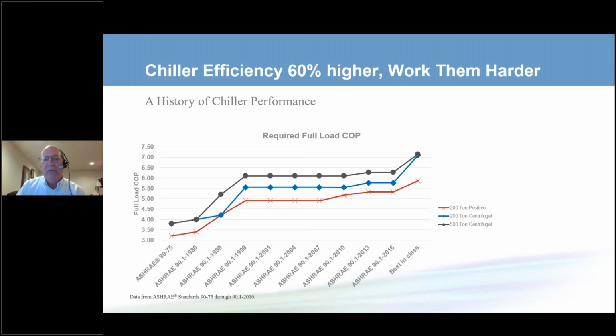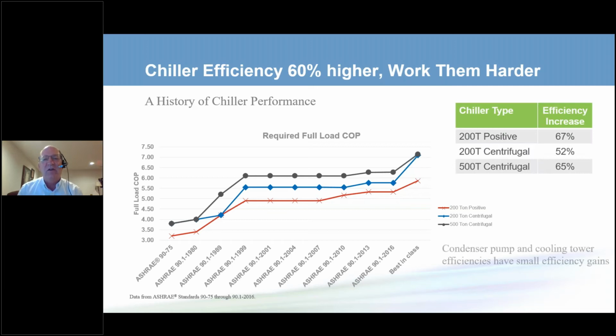We see that there's been a significant increase in the COP, and I really like that societies and cultures like yours use the coefficient of performance. That is, how much useful cooling do we get out of the chiller compared to the work put into that chiller. In the US, we use what I tell people are the wrong units. We use kilowatts per ton, and that's not a good measure of chiller efficiency, but COP really is. And when we look at what COP has done, and these are just the required ones, the efficiency of chillers has increased by between 52 and 67% over the last 45 years.